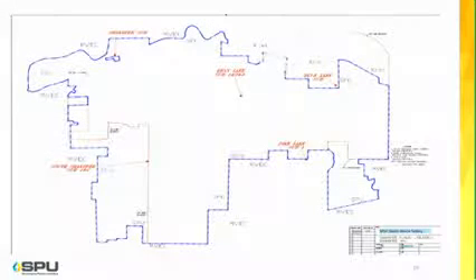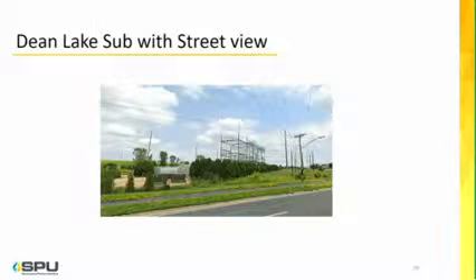So then the next sub is really in the center of our system, and it has most of our facilities in it, appropriately, and it's the Dean Lake sub. Here's a street view of that. You can see those same transmission lines that were at Marshall Road. You kind of see the squat 230 kV tower, but here's the double circuit, 345 on the left, 115 on the right. So additional structures had to be added, wooden structures here to intercept the 115. And this steel structure was here to lift up the 345 so that the 115 can go underneath it. And you can see that this is a bit of a bigger superstructure here at Dean Lake.